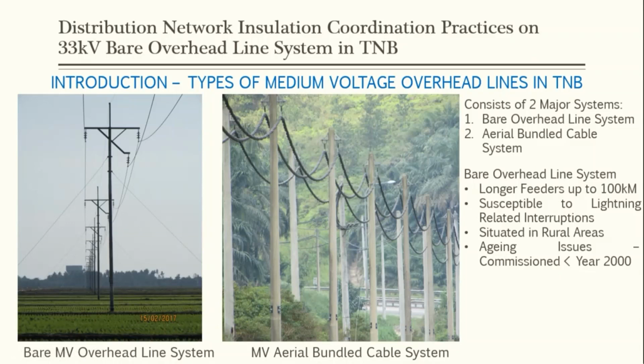Usually, the focus will be on the bare overhead line system because it is more susceptible to lightning-related interruptions. It is usually situated in rural areas, and the bare medium voltage overhead lines are facing aging issues because most of them were commissioned before the year 2000.